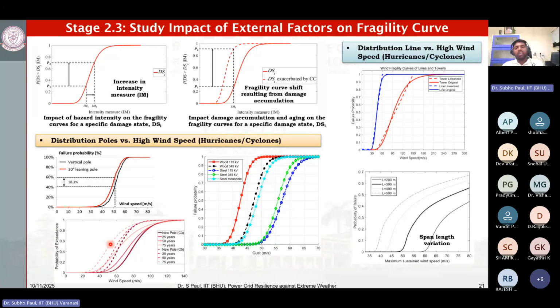Then you have this distribution line. Obviously, those are more brittle compared to your pole. So if you see the comparison between the line and the tower or the pole, the line is more brittle. That is the blue one. That has the higher probability of failure at a low speed event. Now the span length, that means the span between two poles. If you are increasing that, that means the hanging distance of your distribution lines is also increasing. So that has a very high probability of failure when the wind attacks. But if the span is very short, then your probability of failure is less.